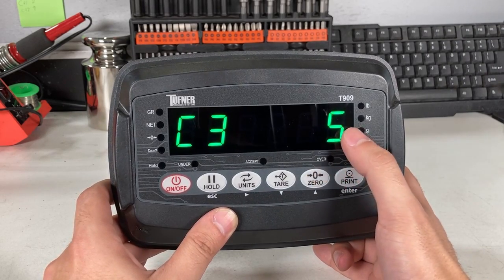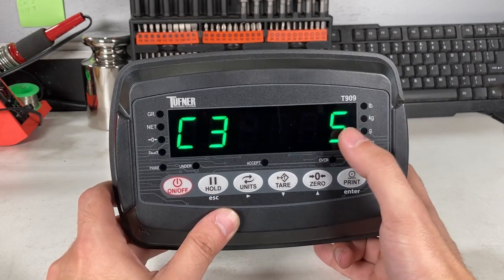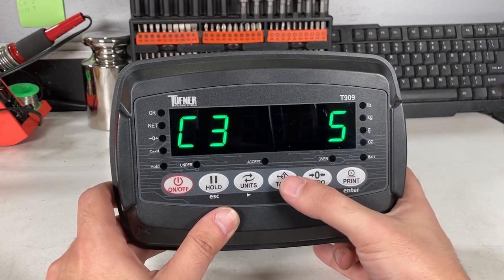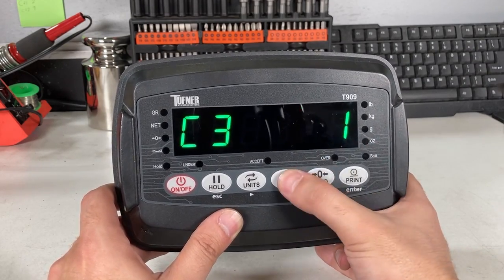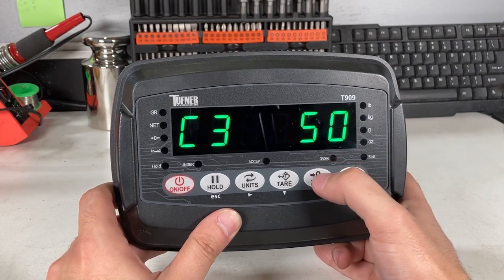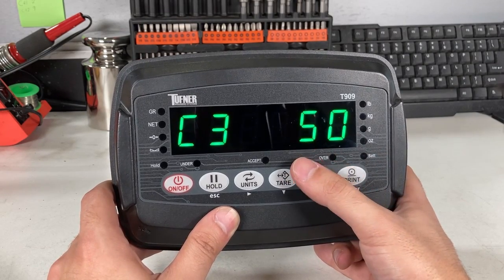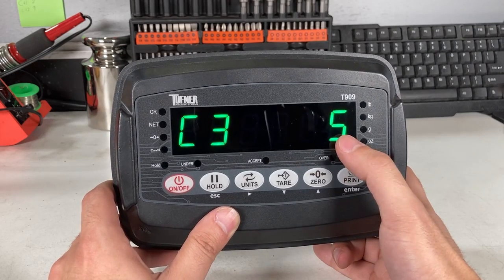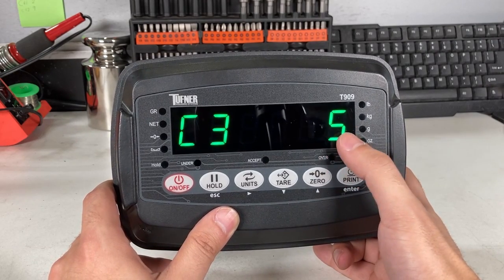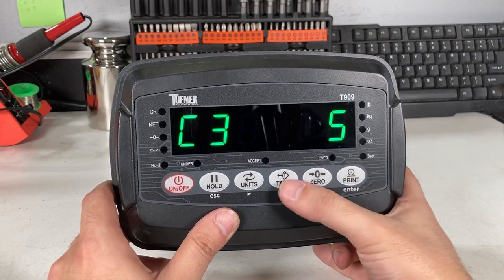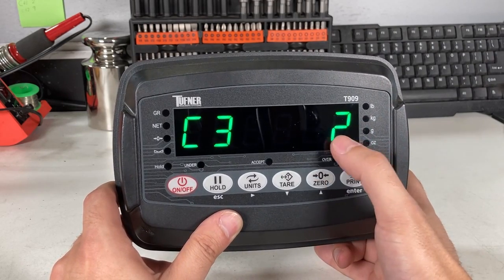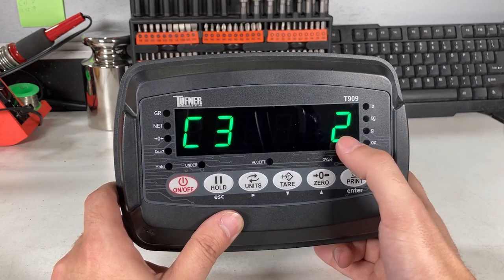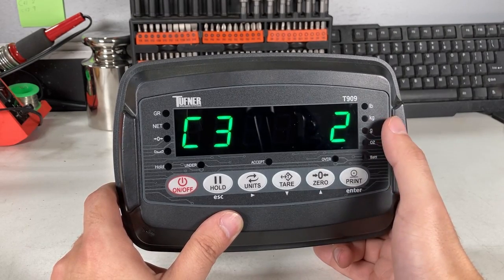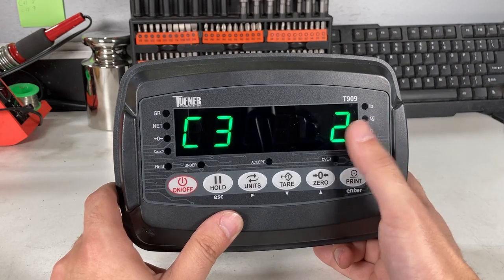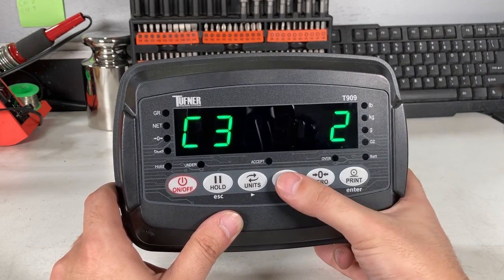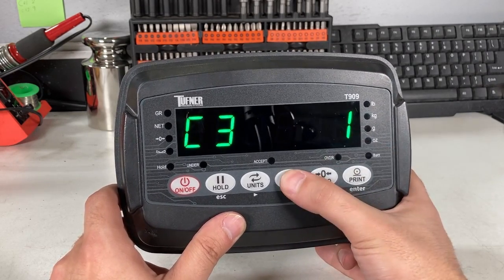C03, this is what it's counting by. Right now it's counting by 5s, and since I put 0 decimal places previously, it will be 5 pounds. This is by 2, this is by 1, right? This will be 50, so it counts by 50 pounds. If this was 1 decimal previously, counting by 5s would mean half a pound accurate. This will be 0.2 pound accurate, counting by 0.2s, and it will just round up or down. Since I put 0 decimal places previously, this will be 2 pounds.